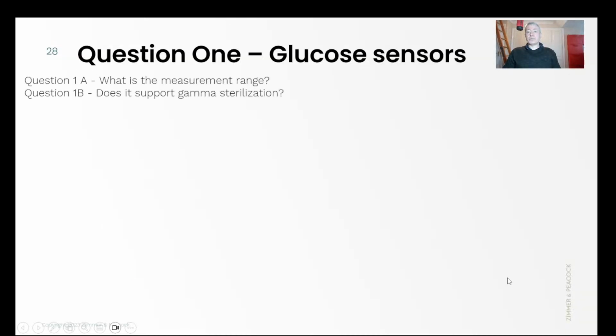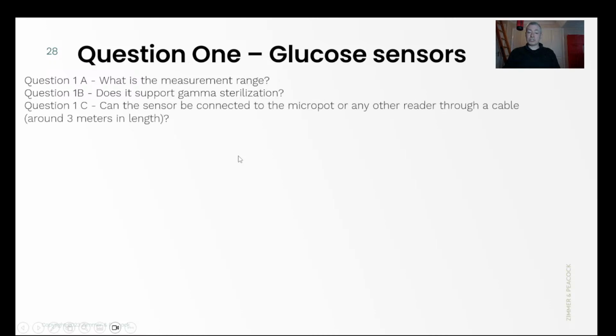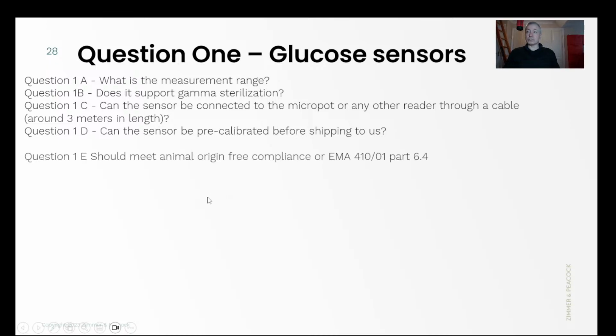So what is the measurement range? The measurement range is 1 millimolar to 1 molar, which is basically 3 orders of magnitude, but we would tune the sensor based on what the client was expecting. We do support gamma sterilization. We're doing sterilization studies even as we speak. The 3 meter length cable, I'm confident on it, but we'd have to do a sort of mini project in order to test it. Please get your phone out, follow those QR codes. You'll see that we have a way of taking data from our factory out into the field using QR codes.